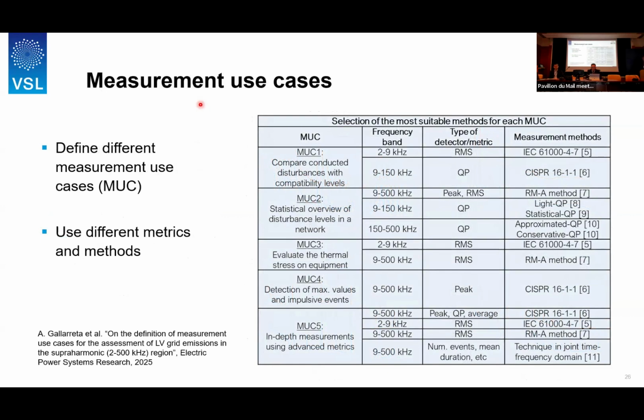So what they also did is they considered several of the standards that are already available, and they realized that you might have to define different use cases, which sounds logical, but nevertheless it's good to define that. For instance, here are these measurement use cases, 1 to 5. You might compare conducted disturbances that you find in the grid with compatibility levels. That's one application. You might also do a statistical overview of disturbance levels in a network. That means how often do they occur, per week, per year, whatever.